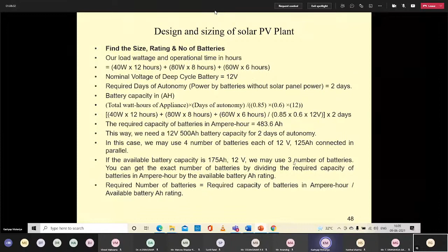Now you have this type of panel module specification with you. When I designed these things for places at Surat, I was also given a specification of VOC, peak power, nominal voltage, peak voltage, sorry, and ISC that we have already defined. What is ISC? So the required solar charge controller is: I have total 5 modules or 5 panels times the ISC, that is 8.8 ampere, times 1.25. Now this 1.25, how it comes, is also a debate that you can also correct. So it means for the charge controller sizing, I need at least a capacity of 55 ampere here.